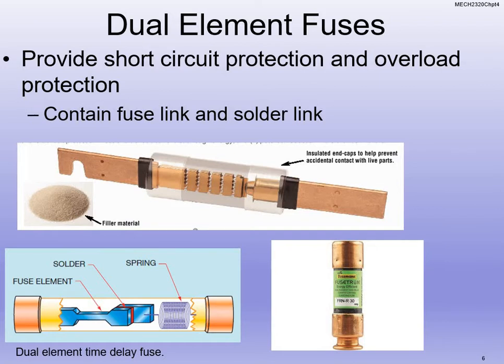So if it draws too much current for too long, then it will break. But if it draws a lot of current and then sips back to normal, that solder will re-solidify because it won't be hot enough to melt it. So the fuse won't necessarily trip. So that's why we use time delay fuses.